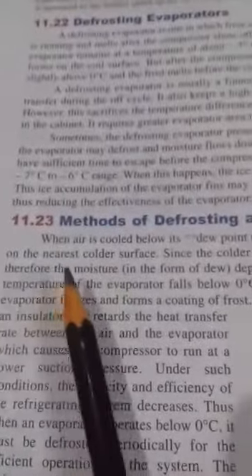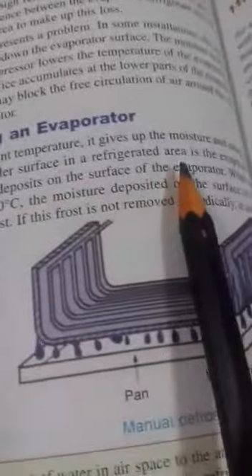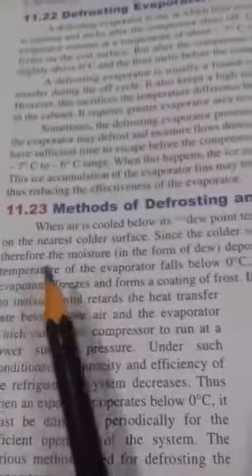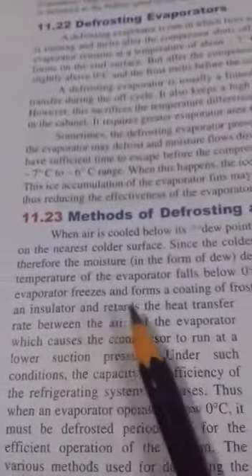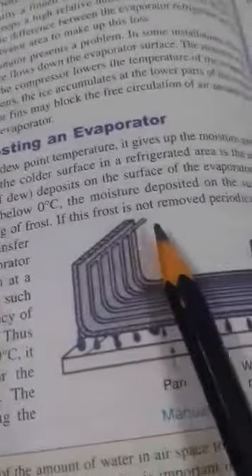Let us discuss the method of defrosting. An evaporator is defrosted when air is cooled below its dew point temperature — it gives up moisture and deposits it on the nearest colder surface. The colder surface in the refrigerating area is the evaporator, so moisture in the form of dew deposits on the evaporator surface. When the evaporator temperature falls below zero degrees centigrade, this moisture freezes and forms a coating of frost.